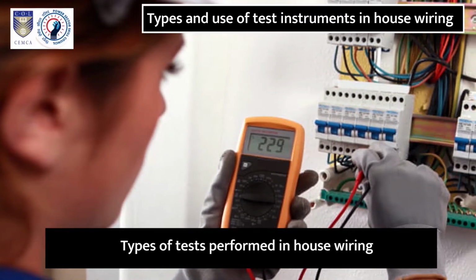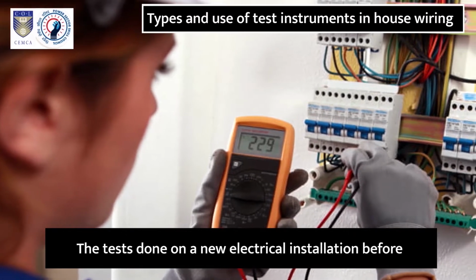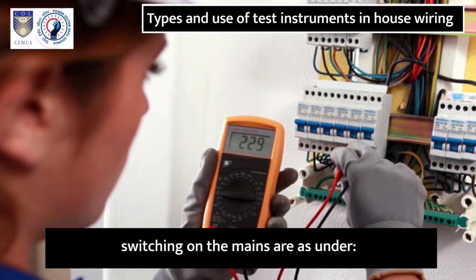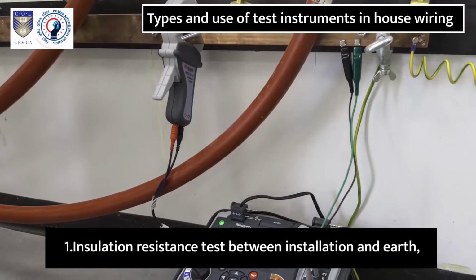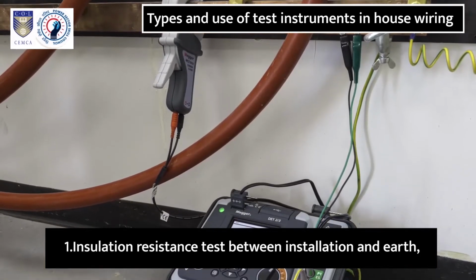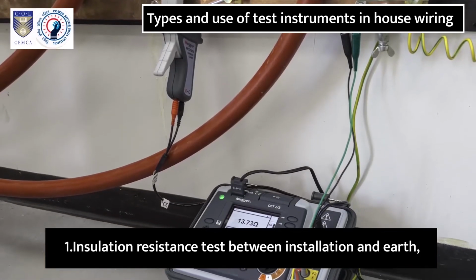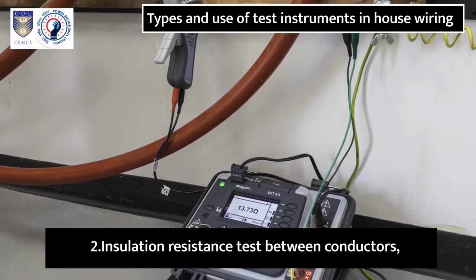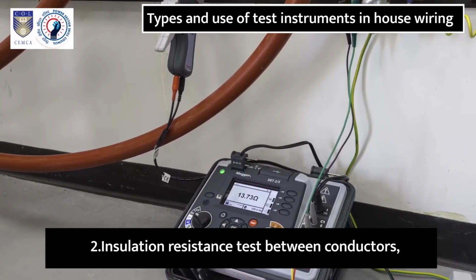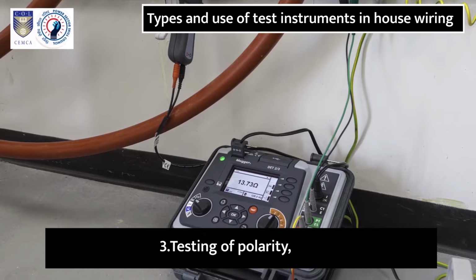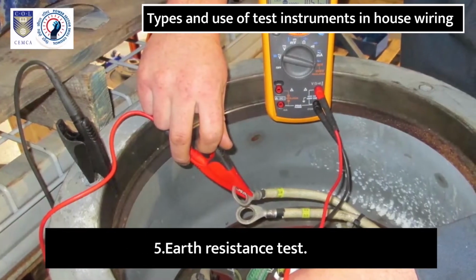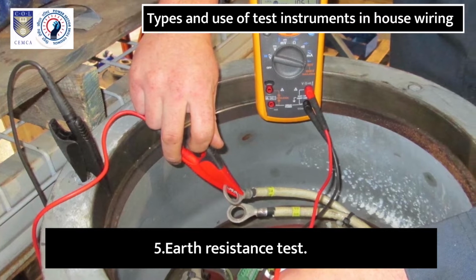Types of tests performed in house wiring. The tests done on new electrical installation before switching on the mains are as under. 1. Insulation resistance test between installation and earth. 2. Insulation resistance test between conductors. 3. Testing of polarity. 4. Testing of earth continuity paths. And 5. Earth resistance test.